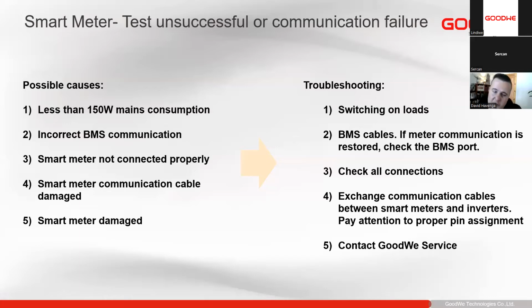Next, if there is an issue with the BMS communications, the smart meter test may also not complete. So then we can fault find the batteries. If the smart meter is not properly connected, like I said, we can extend that cable. The smart meter communication cable, the one in the box, sometimes we route it and it might get damaged or something like that. Or if we use an RJ45 extender, those network extenders are not designed for RS485 communications and can cause interruptions. So never use a network extender plug to run a longer cable. Always replace the entire cable. That way there are no points for interference. The RS485 is very susceptible to external magnetic fields, and anything like that can cause the communication to fail.